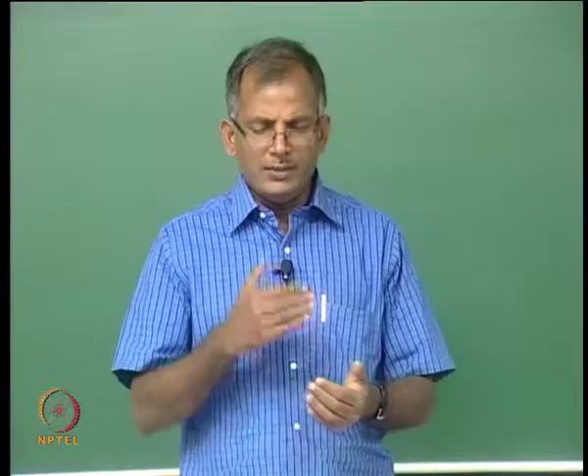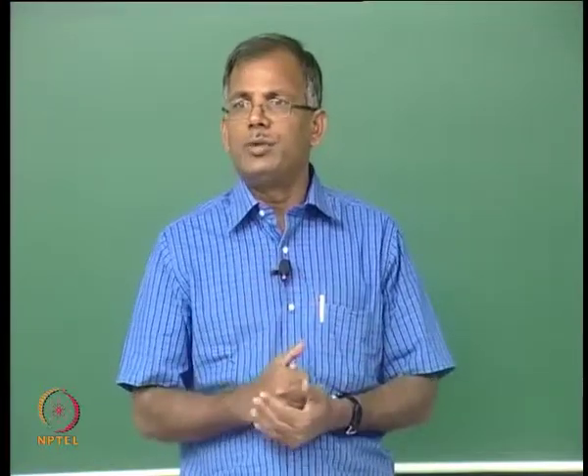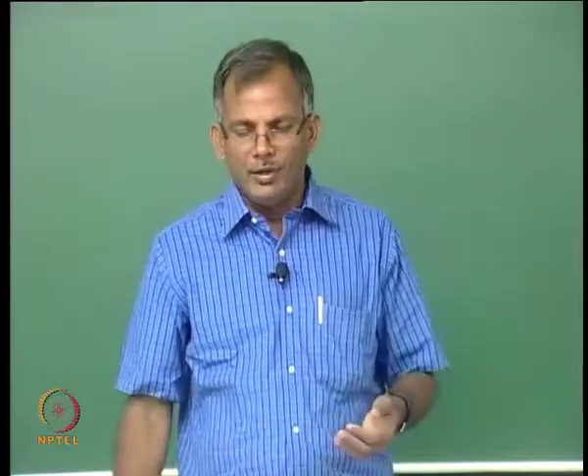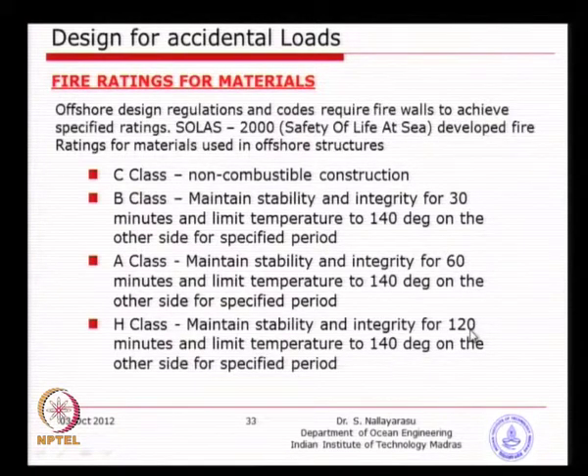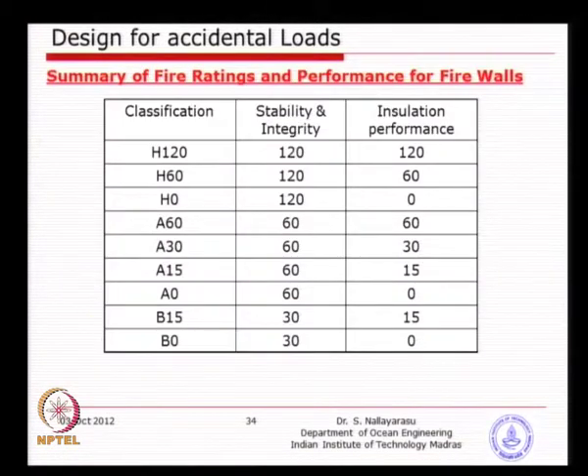H class has stability and strength for 2 hours, A class for 1 hour, and B class for half an hour. The subscript number — for example H120 versus H60 — indicates the insulation performance in minutes. H120 means 2 hours of stability, strength, and insulation; H60 means 2 hours of stability and strength but only 1 hour of insulation performance. This is how the firewall characteristics are defined.